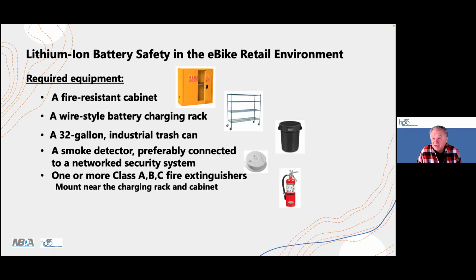One or more Class A, B, and C fire extinguishers — this is not to try to put out a lithium-ion battery fire. A fire extinguisher will not extinguish a lithium battery fire. If a battery catches fire, you cannot put it out. All you can do is try to control the fire and mitigate the possible damage associated with it, and we'll talk about that in more detail.